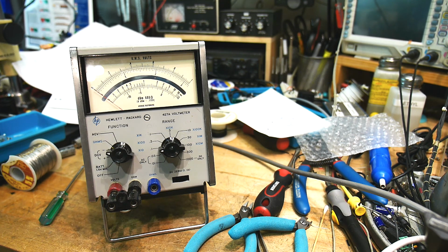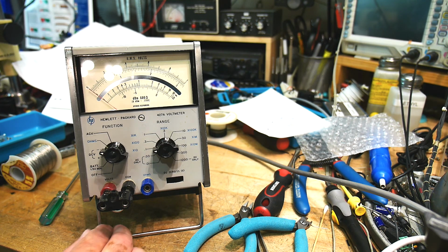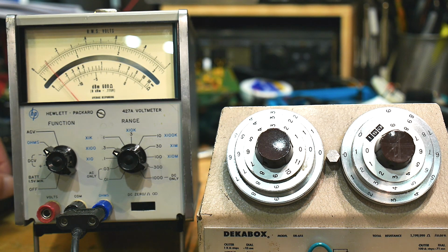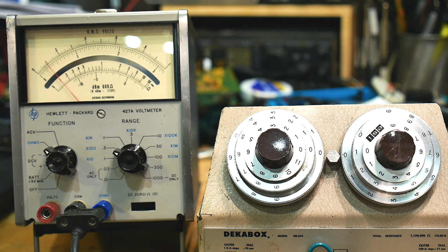Oh, this is complicated. I'm going to do this off camera. Okay, I got it all calibrated, and that worked out just fine. The way that you do it is you do a kind of crude DC calibration for offsets and stuff, and then you go through the AC calibration part, where you put in a 400 hertz signal, a 1 kilohertz signal, and a 100 kilohertz signal. And there are adjustments inside for those things. And then you go to the ohms adjustment and adjust those on several ranges. And then you go back to the DC and you calibrate those for 3 different ranges.